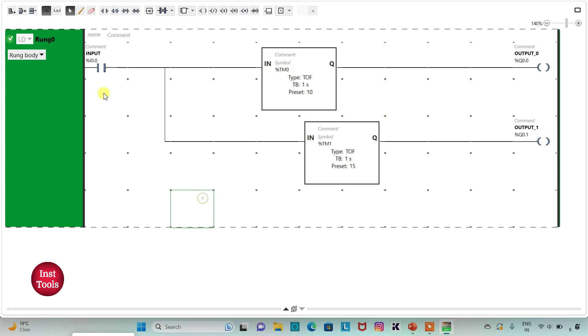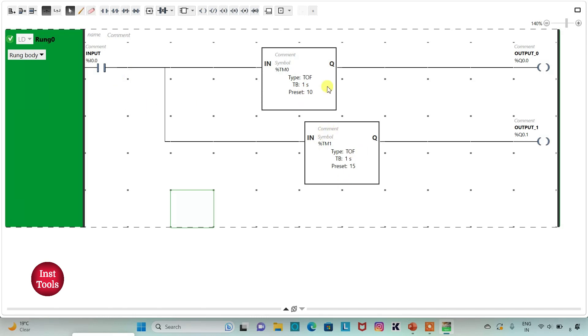I will change the time base to 1 second and the preset value to 15, then click Apply. When I turn on the input (I0.0), output 0 and output 1 will both be on. When I turn off the input, output 0 and output 1 will still remain on — output 0 will remain on for 10 seconds and output 1 will remain on for 15 seconds. After 10 seconds, output 0 turns off, and output 1 turns off after 15 seconds.